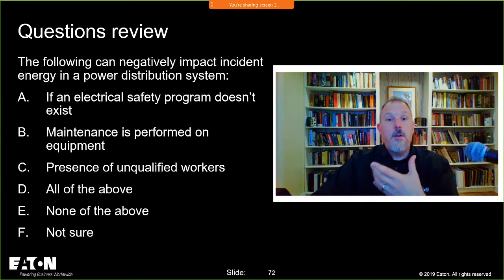But I can't rely on a circuit breaker to clear if I haven't performed maintenance on it. And if that circuit breaker doesn't clear fast enough, then I am into a situation where my incident energy at the location that I'm working could be higher than what I expected. I would use this as an example. If I'm working at this location in the power distribution system, I'm relying on a circuit breaker up here. But if that upstream breaker has never been maintained, has never been operated in years, then I don't know if that overcurrent protective device is actually going to do what I'm hoping it does and function and operate. I need to understand what my hazard is and the condition of maintenance of that upstream overcurrent device. I need to be able to recognize the electrical hazard.